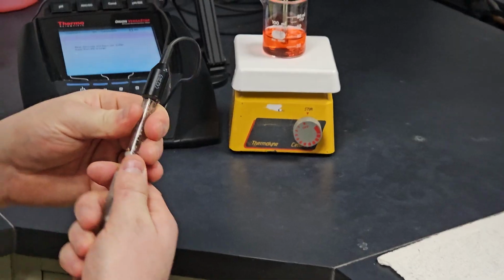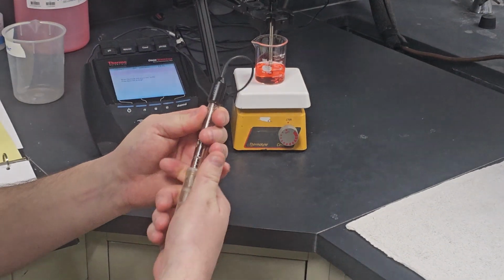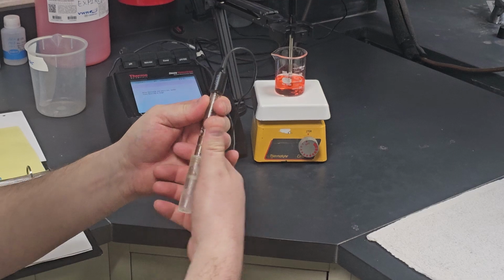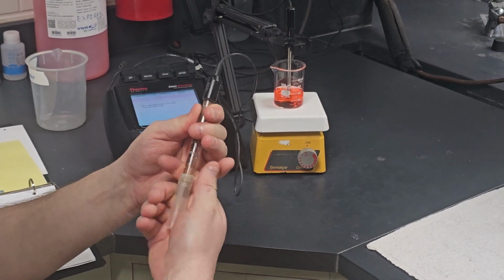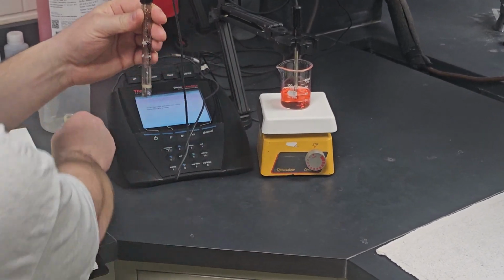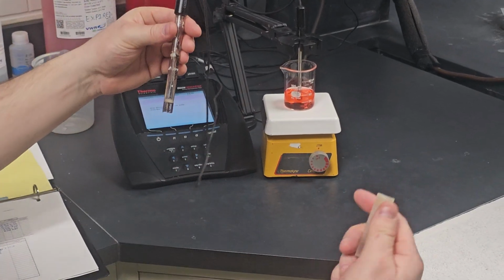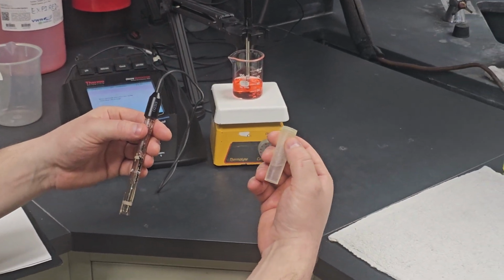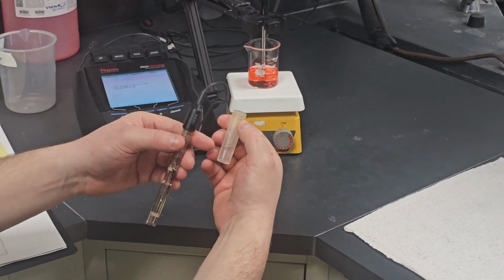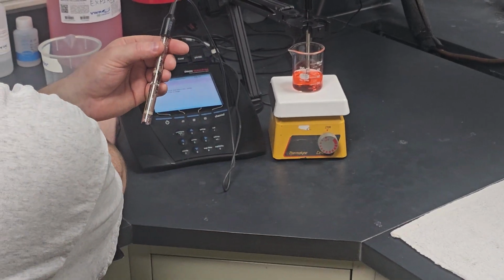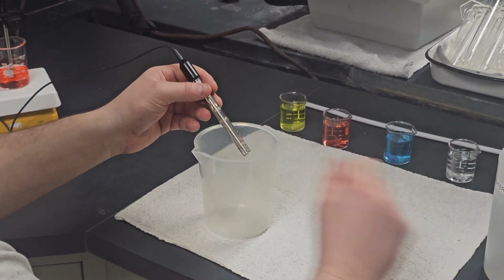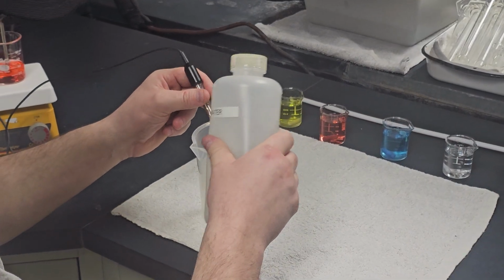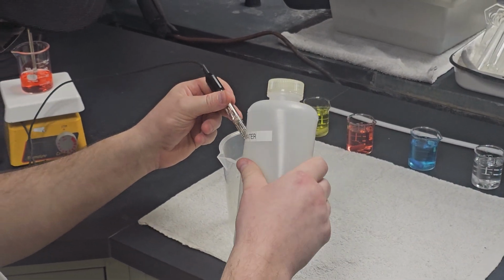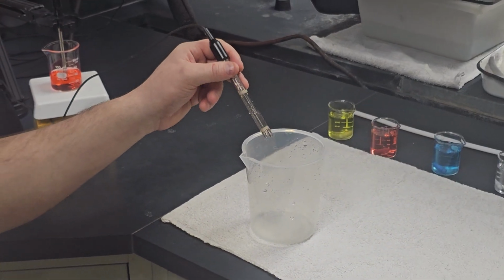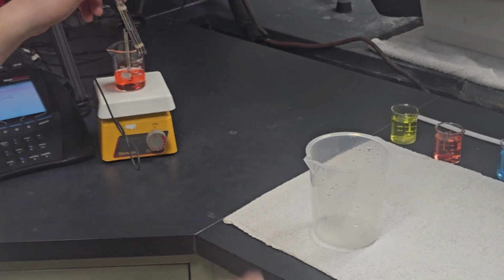We take our probe out of the sleeve by gently twisting. You don't want to rip it right off, and you don't want to squeeze too hard. Just gently twist it off of the probe. You'll notice that there's some storage fluid in the bottom of the probe tube. Make sure not to spill that. So set that upright out of the way and rinse the potassium chloride off of the probe. Give the probe a good rinse. A very gentle shake to get excess water off.